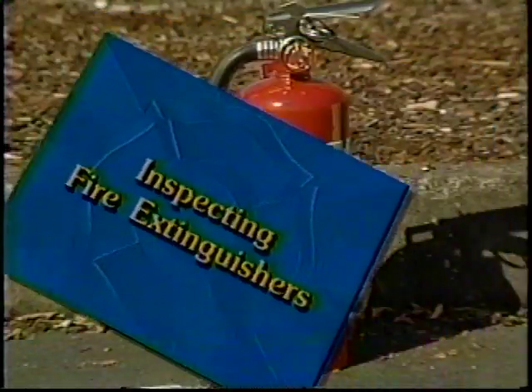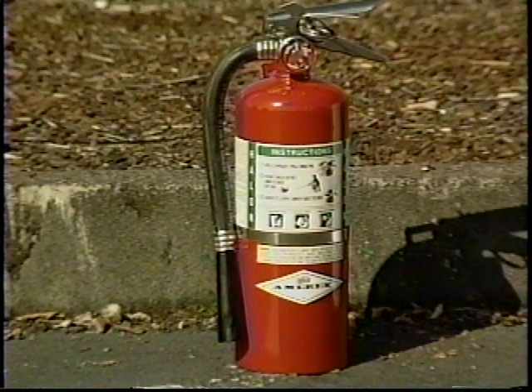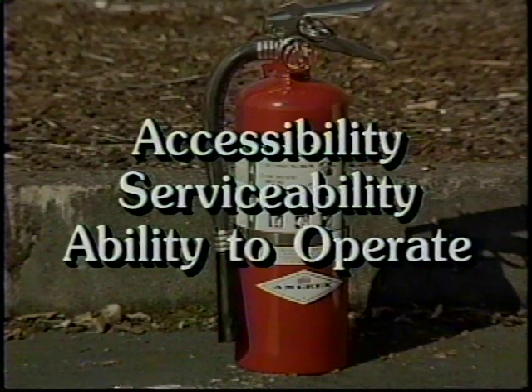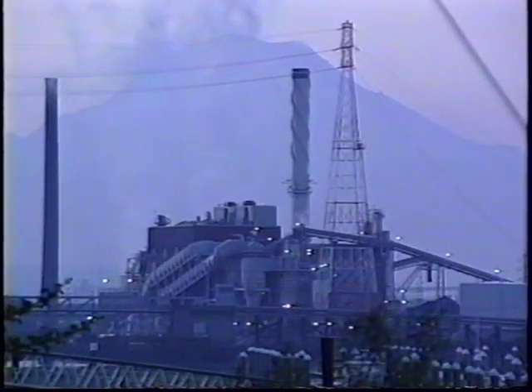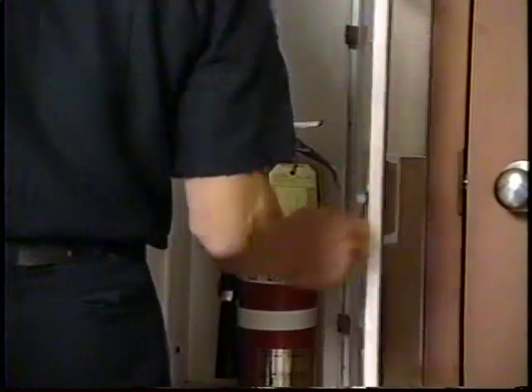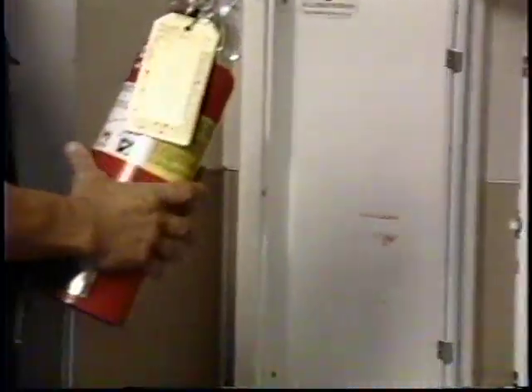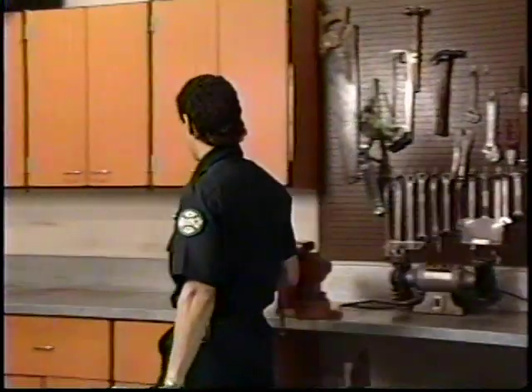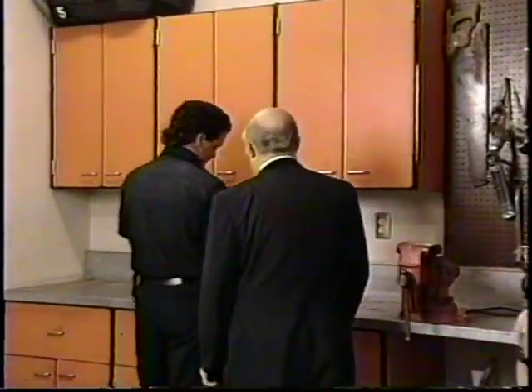To be ready for immediate and effective use, portable fire extinguishers must be regularly inspected and maintained. The three important factors that determine the potential effectiveness of a fire extinguisher are: first, accessibility; second, serviceability; and third, ability to operate. Determine accessibility by checking that the extinguisher is in the correct location and that it is easily accessible. Check to see if you can easily read the operating instructions on the extinguisher faceplate.